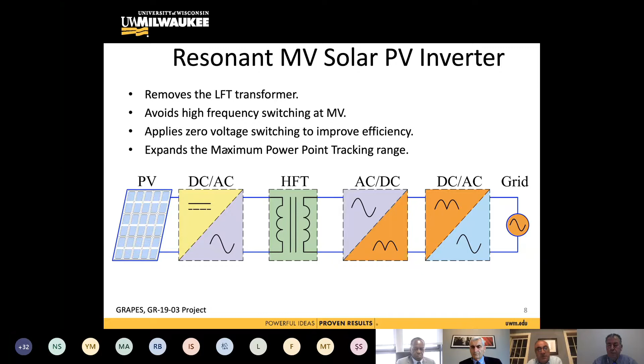The third project falls into the same category and uses the same concept. When you have medium voltage grid in the US, what you see on the left, the distribution voltage from the utility company, the lowest voltage you get is 13,800 volts, so 13.8 kilovolts. And then how you can get that AC voltage and directly generate 1000 volt DC. This 1000 volt DC would be at high power, and it can be used for fleet charging of electric vehicles. So you can have vehicles there, either onboard or off-board chargers, from 1000 volt DC and charge several vehicles. And doing that, you have isolation from the grid.